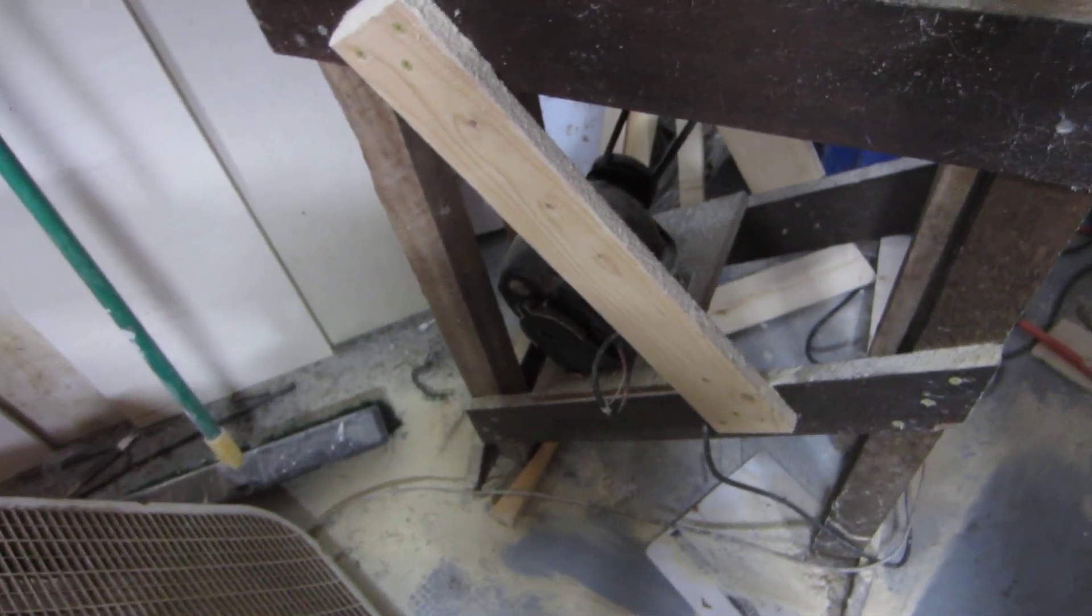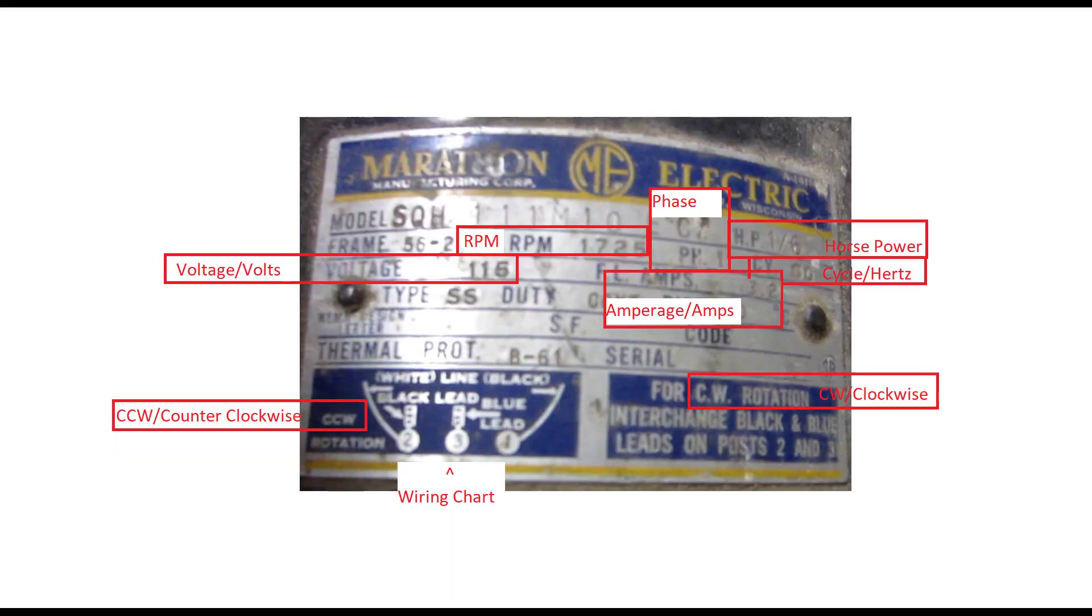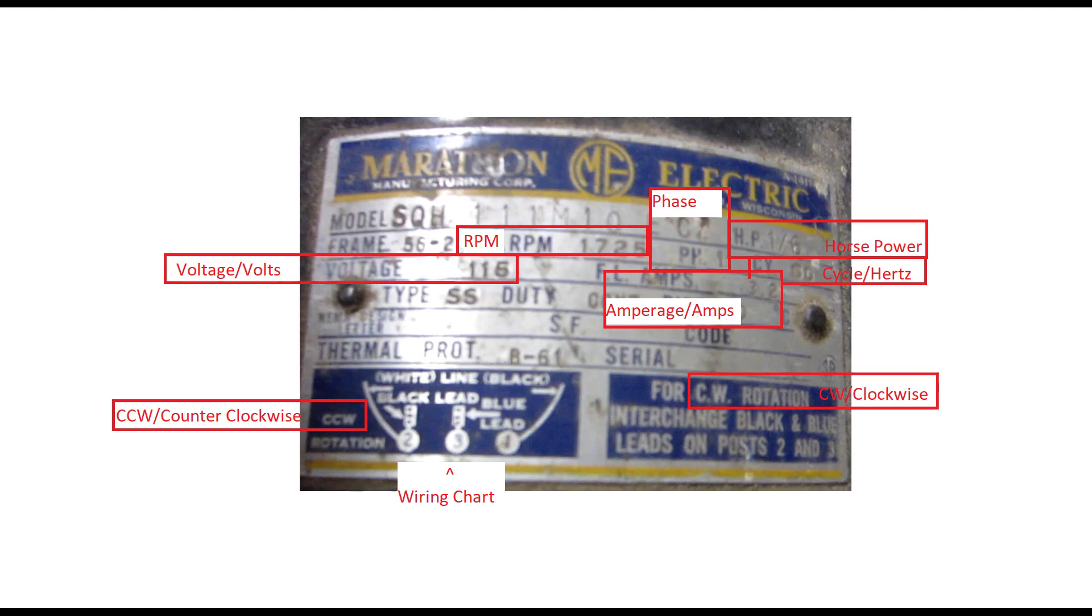The really important stuff you need to match if you're replacing a motor: the voltage, which would typically be 110 to 120 or 220 to 240, the RPMs or rotations per minute should be the same, the horsepower should be the same or greater.